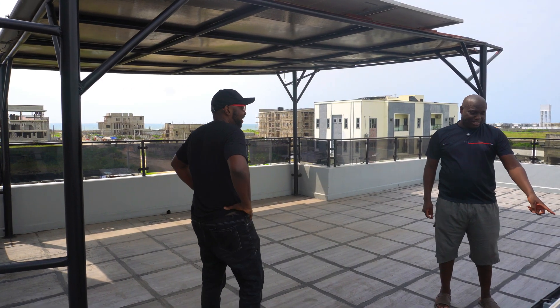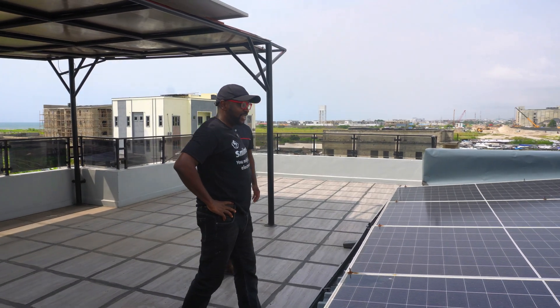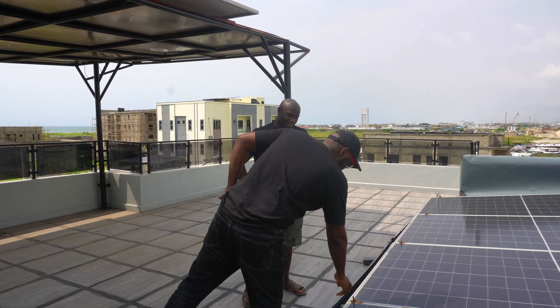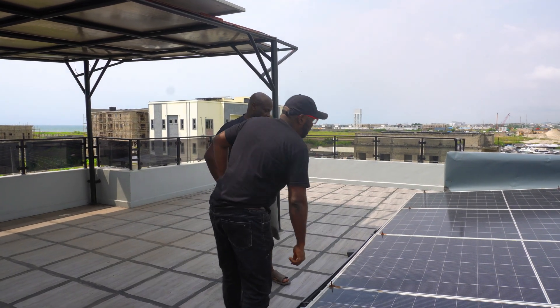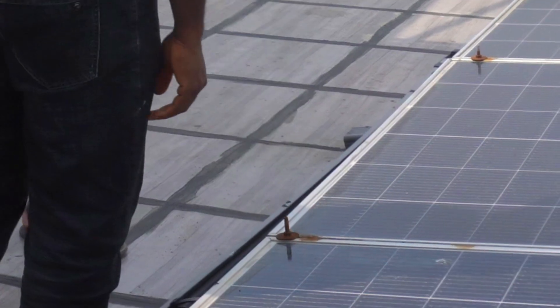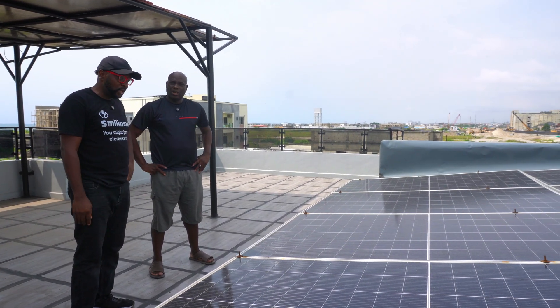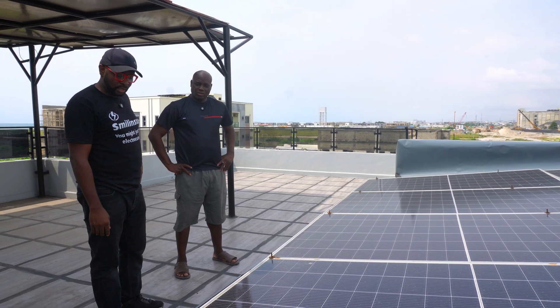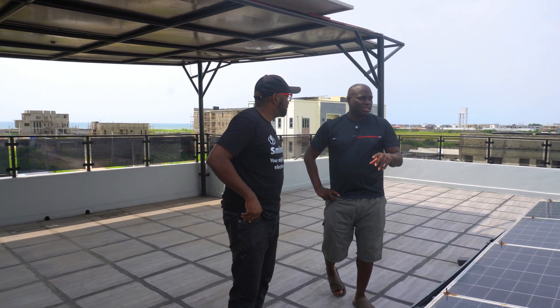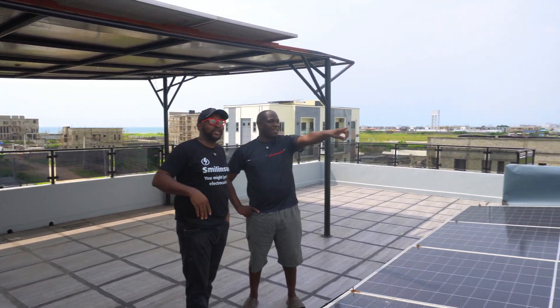We'll verify the 670-watt rating — that's where we need to start. Right here they should have used proper metal clamps; these are not adequate — you can see they're already rusting because of the ocean environment. They were meant to use metal L-foot clamps and proper clamps so they don't rust. But what's done is done.